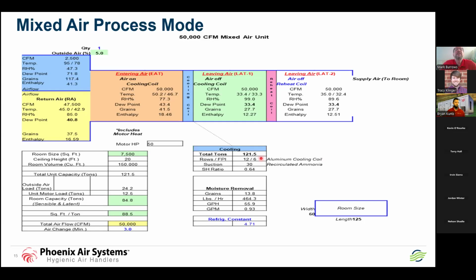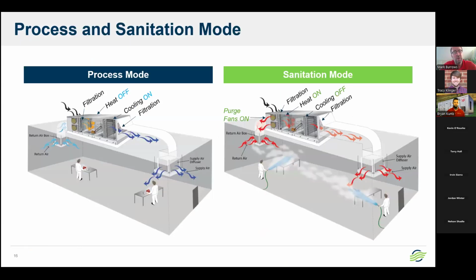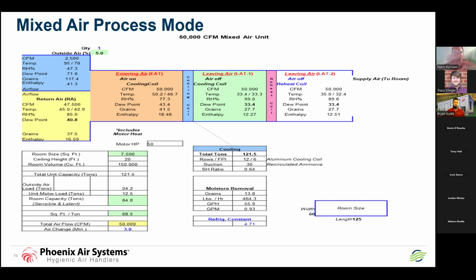The suction, again, is at 30. The sensible heat ratio is 64%, so that much of it is going to be sensible. The other 36% is going to be latent work. That's where we're taking moisture out of the airstream. And other details, not that it matters for this discussion, we can actually tell the client exactly how much moisture we're taking out, GPMs we're condensing at a given time. Any job that we do, whether it's a small job or a large job, you're going to see the same sort of evaluation as far as the psychrometrics.